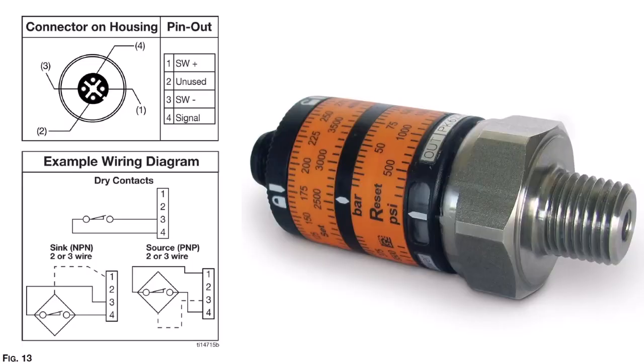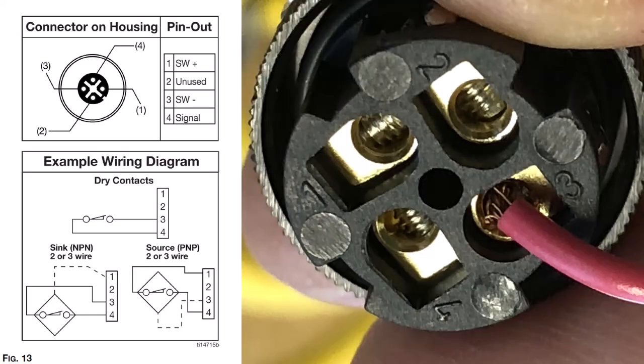If this is a new installation, double-check your wiring diagrams and verify that the cable has been wired to the connectors correctly. Some sensors have 3 wires that need to be connected, and the pin assignments on these sensors can vary from one to the next. Dry contact switches typically only need 2 wires, and these wires need to be connected to pins 3 and 4 on the G3's M12 connector. You're going to want to have good lighting or you won't be able to make out these little numbers.